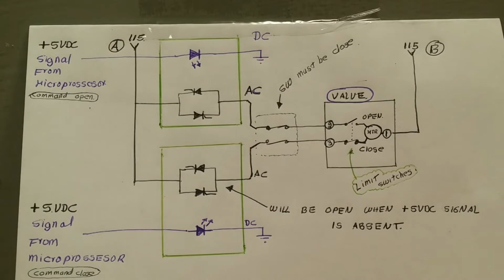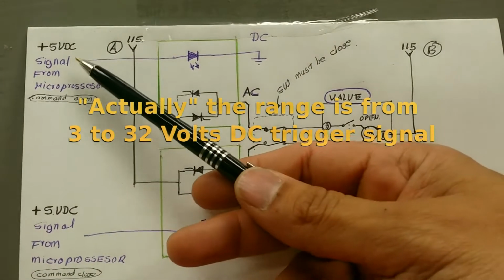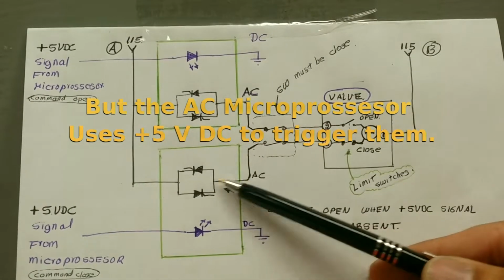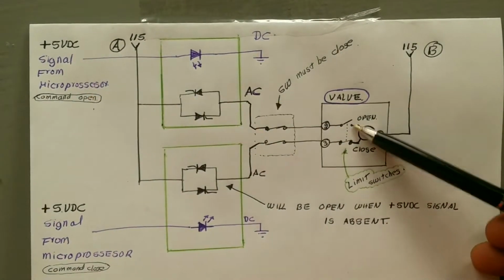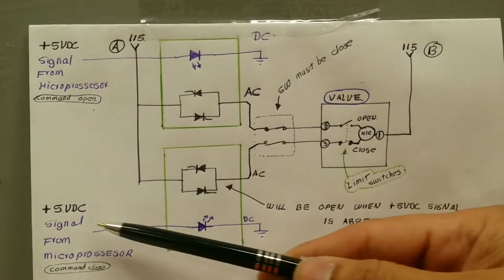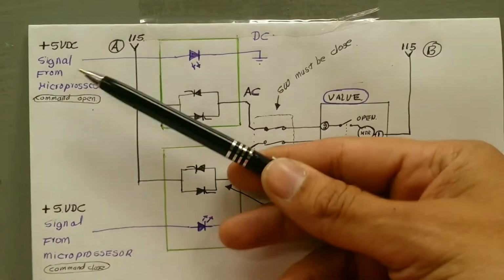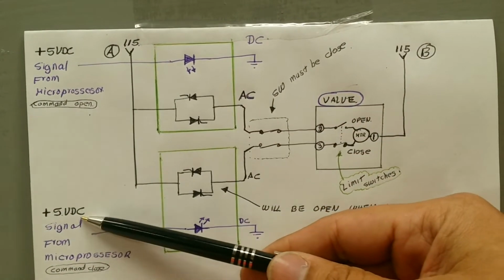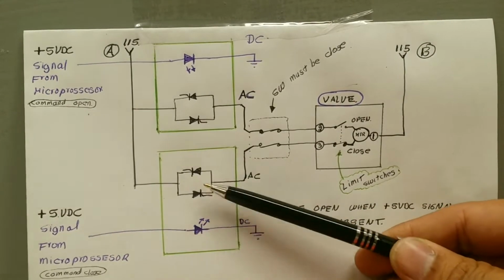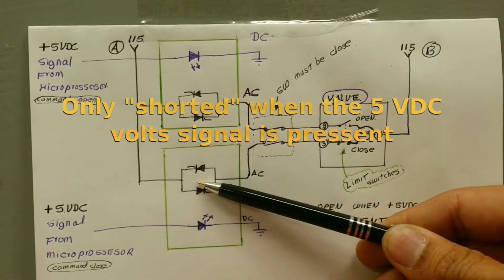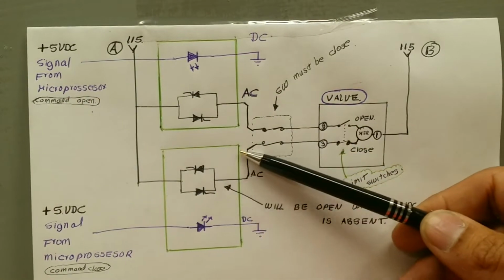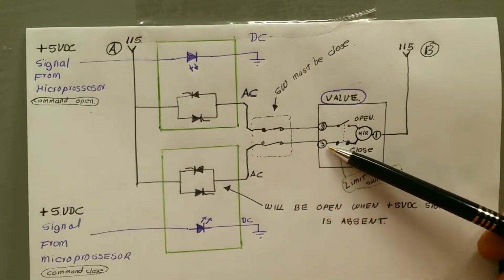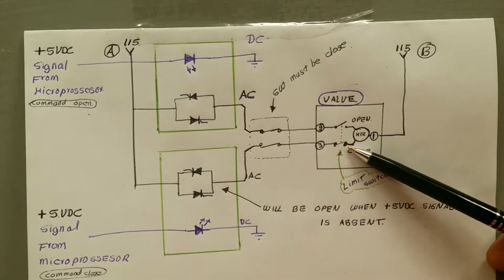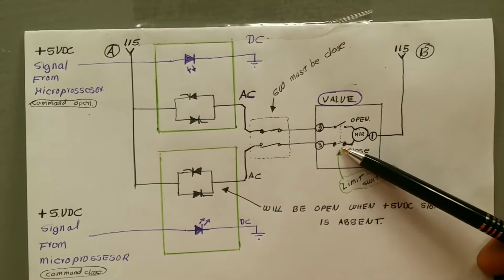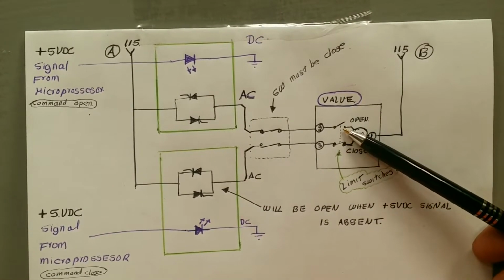An SSR, I covered this in a previous video, but a quick review. An SSR is a device where we can use a small 5-volt signal to control a larger AC load like we do over here. We're trying to open this valve over here. The valve is already closed, so let's decide to open it. The microprocessor will always have 0 volts over here and 0 volts over here, but when it decides to open the valve, it will put 5 volts at this point, and it will short this over here. Normally it would be a solid state short, and it will put 115 volts through this switch over here, which must be closed, and this switch is already closed. The valve will start opening, and this will not open until the valve is fully open, and then obviously that one will close until the valve is closed.